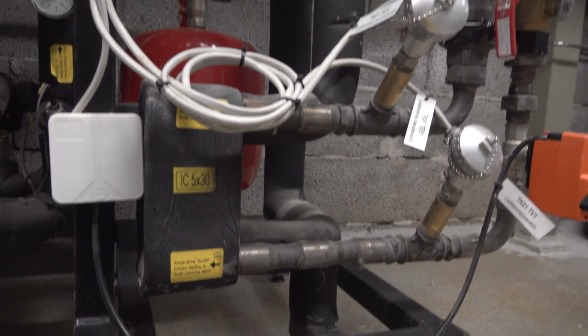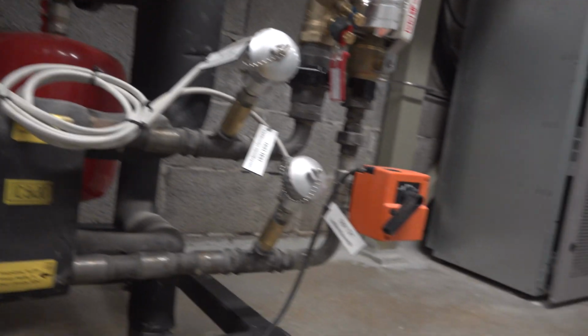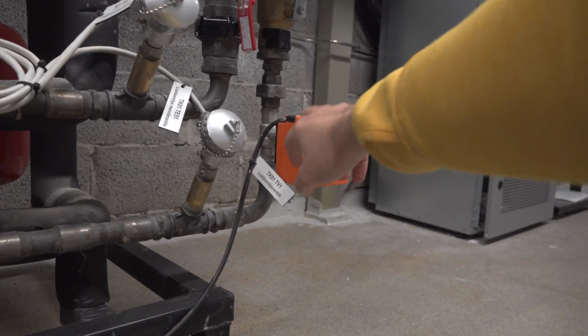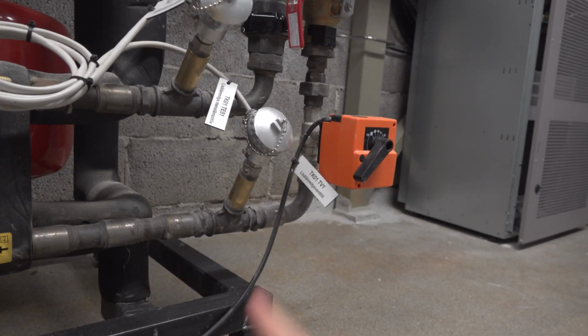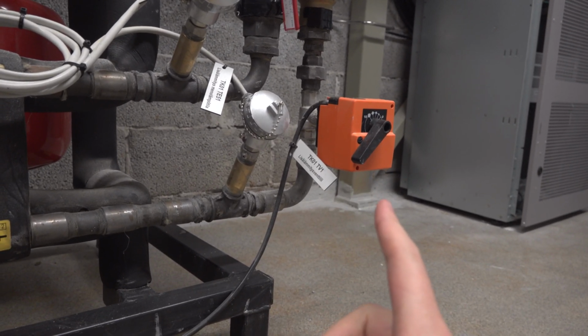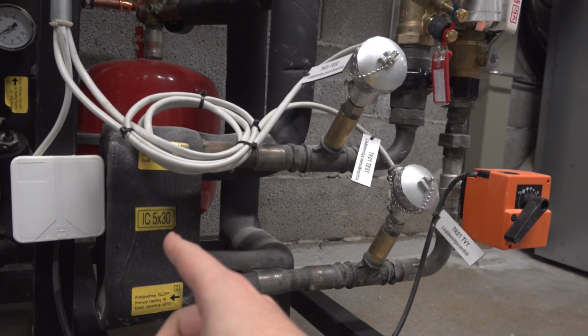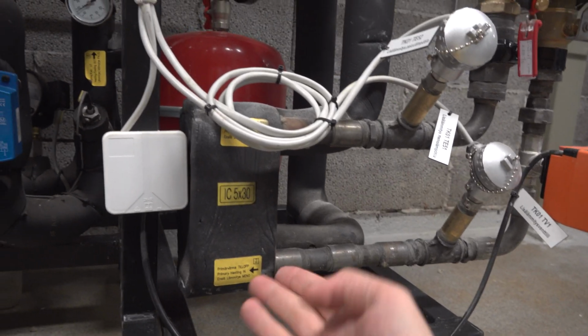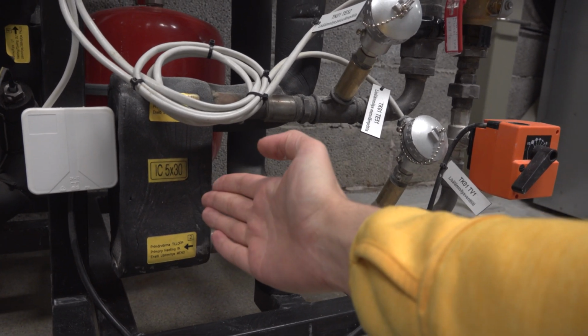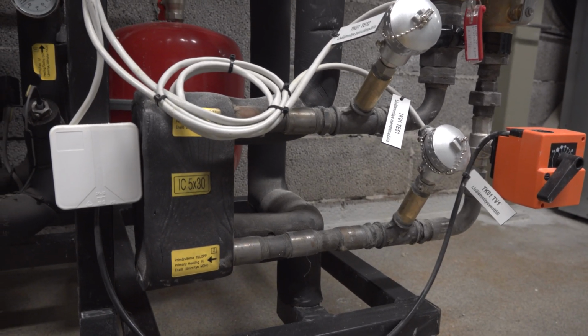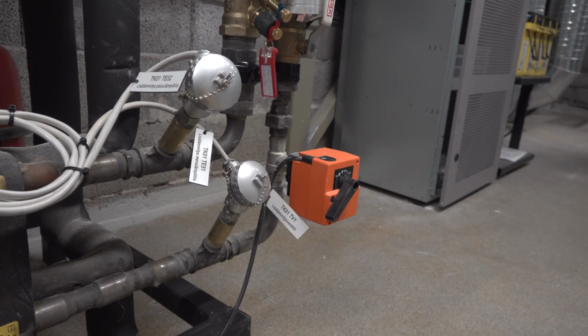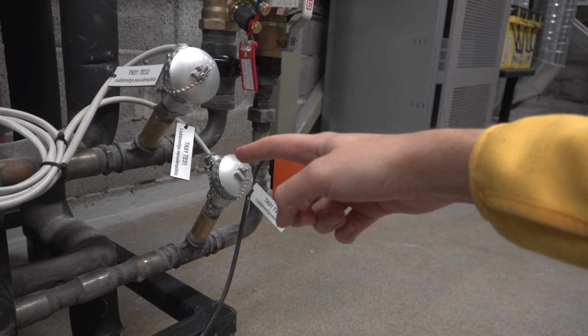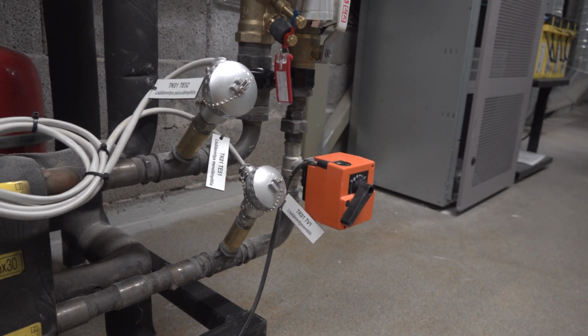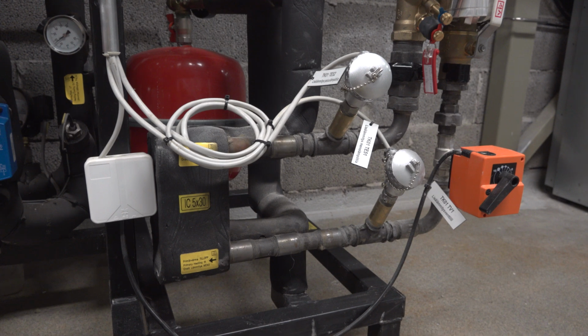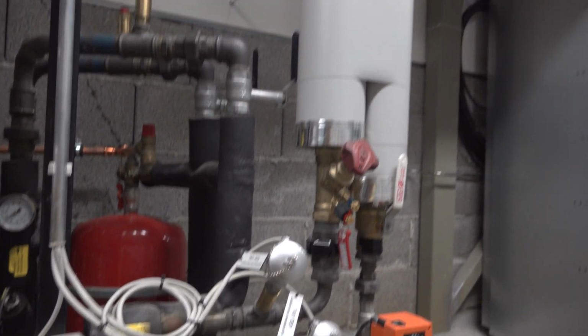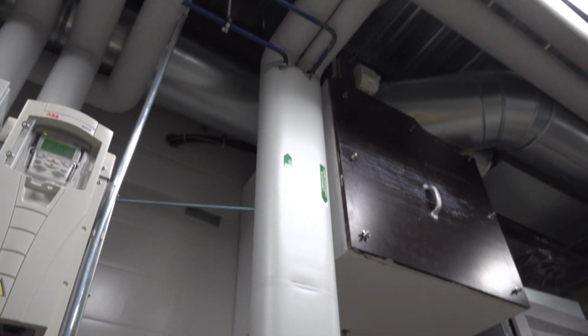There's no circulation in there. There is an additional heating valve here, which is computer controlled, and that thing decides based on the outside temperature if it needs to be adding more heat into the system or not. What I find amazing is that this small thing is enough to heat the whole apartment building's air. It's tiny. Here we have the thermostatic valve and two input and output thermometers that we can see in the software. We are currently on the roof of the building, but these tubes here go to the basement where there is a secondary heat exchanger.